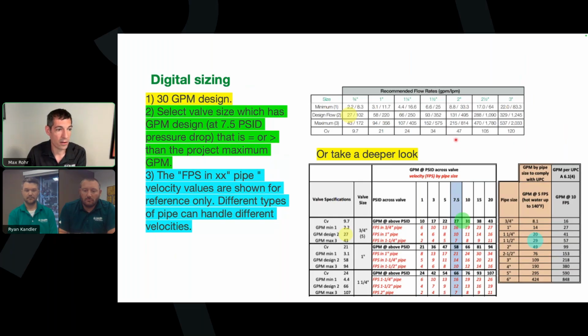So if you had somebody, Matt, call and say, I can't quite go there, I want to go with the 1 inch valve instead of going all the way down to a 3/4 inch valve, what would you notice that would be a little bit different with a 1 inch valve versus a 3/4? Would it still work? Oh, it would, yeah, it would absolutely work. You would have a lower pressure drop than you would through the 3/4. And the main thing is to make sure that your recirc system is able to keep up with that minimum flow rate. It's only a GPM more, really in the whole scheme of things, when you're talking about a system delivering 1.5 inch hot water out to a hotel or a large building like that, 3 GPM is nothing in something that size. Yeah, so you would be covered with the 1 inch. You spend a little bit more money there, but if that makes you feel comfortable, you are still covered there.